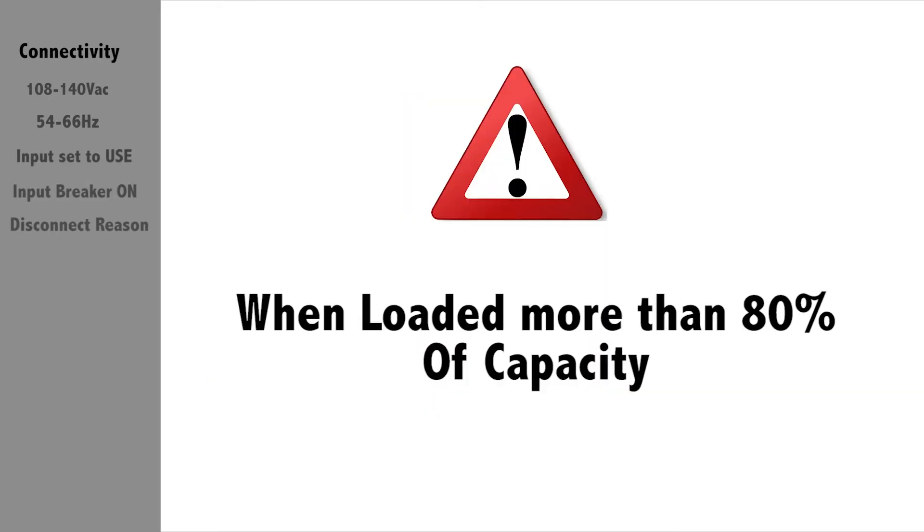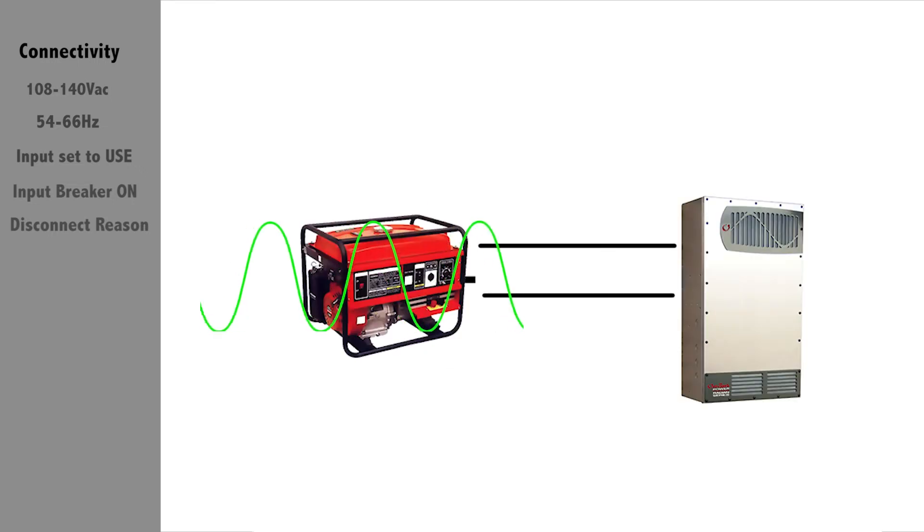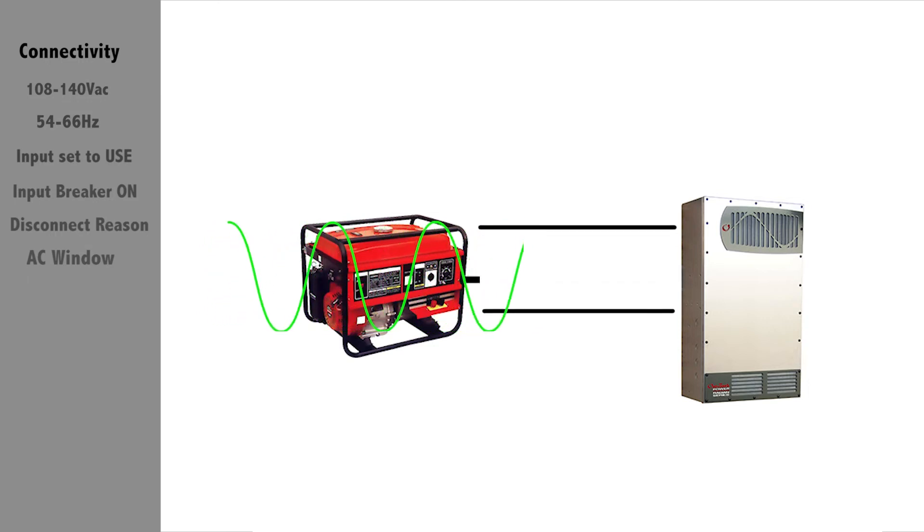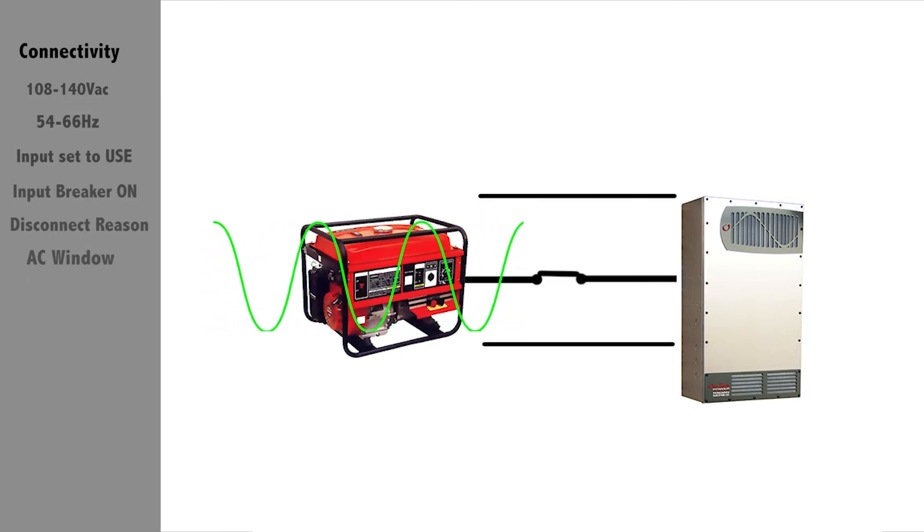Note, some generators are not able to maintain the output voltage and frequency when loaded more than 80% of its capacity for long periods of time. In this case, you may experience nuisance disconnects. The voltage limits can be adjusted to allow a wider voltage acceptance from an irregular generator. However, keep in mind the same irregular power will be passed through your house load.